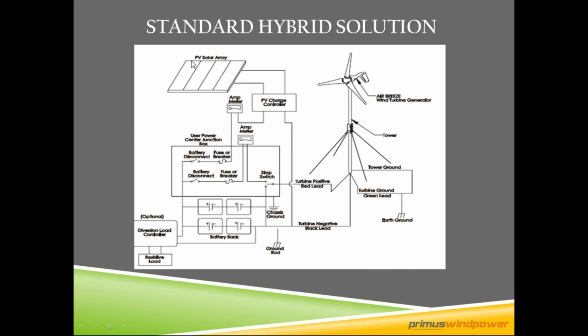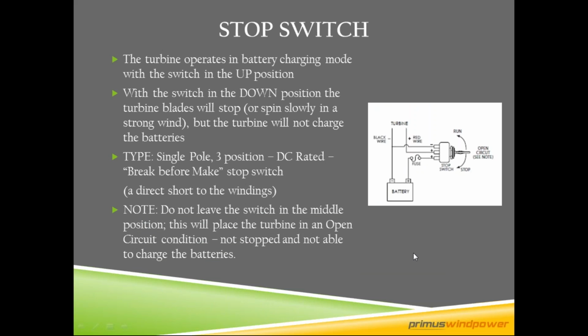Here you have your PV solar array, charge controller, down into your fuse breaker, battery disconnect, into your battery. On the separate side, you have your turbine going through a stop switch—I'll talk about that in a minute—a fuse or breaker, an amp meter if you want to add one into your system, and then into the battery bank. Two separate systems that work really well together.